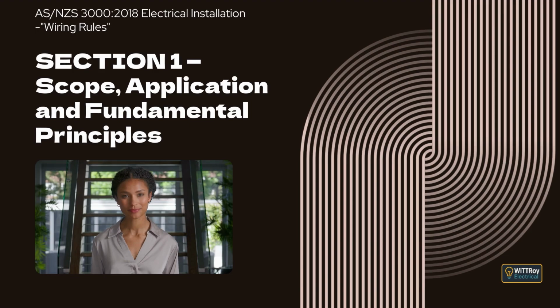Clause 1.4.48 is Earth situation. This is a situation where there is a reasonable chance that a person might touch exposed conductive parts while also touching Earth or some other conducting medium that allows a circuit to be completed to Earth. The following cases are considered Earth situations. Item A. Within 2.5 meters in any direction from a conductive floor, such as concrete, tile, or brickwork, or from a permanently damp surface, or from metallic conduit, pipe, or cable sheath, or any other conductive material on which a person may stand. Item B.